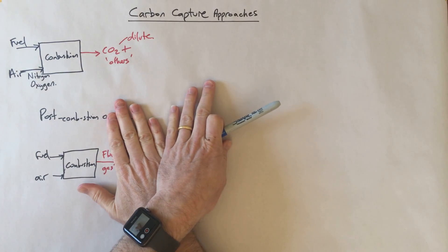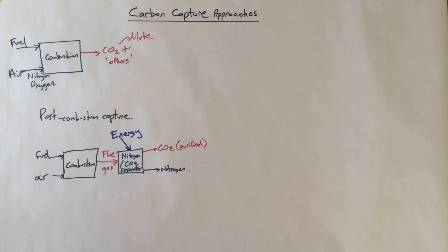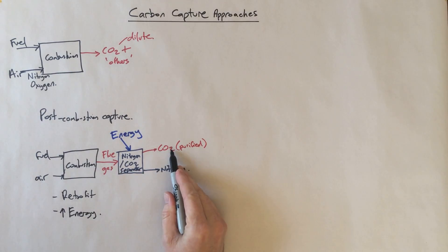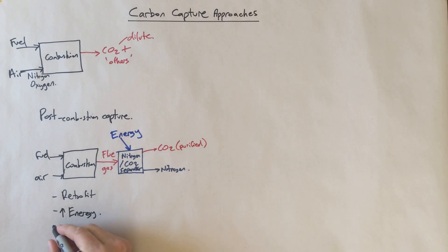This is post-combustion capture, the most obvious thing. We take the plant that we had originally and we can effectively bolt on a purification plant. It's got some upsides in that it's good for retrofitting. So you've got an existing power station or an existing plant that produces CO2 in its flue gas - you can retrofit existing plants with that. It does require a lot of energy. The reason is that this flue gas is predominantly nitrogen, and you're having to process a very large amount of flue gas, most of which is not the CO2 you're actually interested in. And thirdly, it's quite capital intensive.